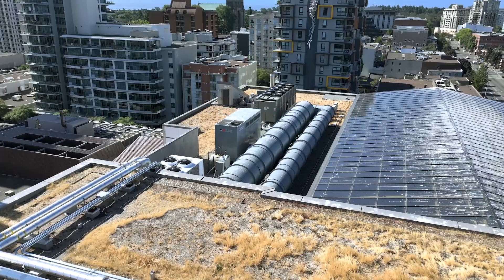We have some fairly detailed programming that picks whether or not we rely on the air source heat pump for our cooling, or we switch over to the chiller and maybe a little bit of supplemental heat from the boilers to keep the building comfortable. It compares the energy performance of both options and then picks when we alternate between the two.